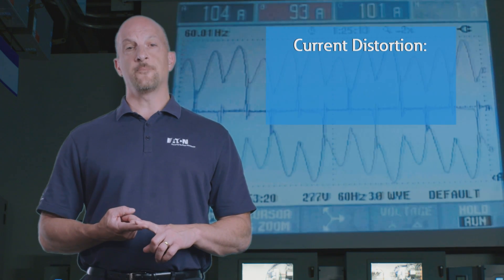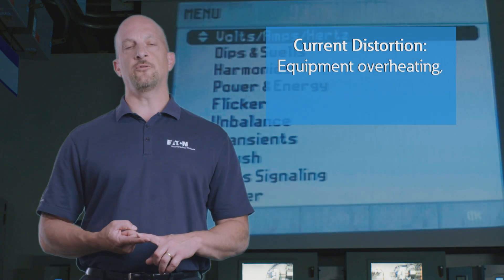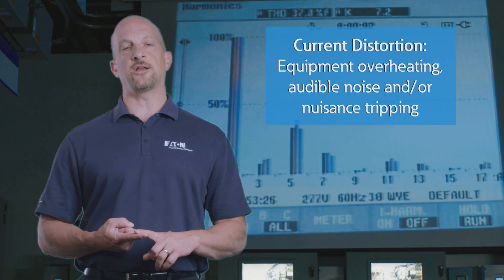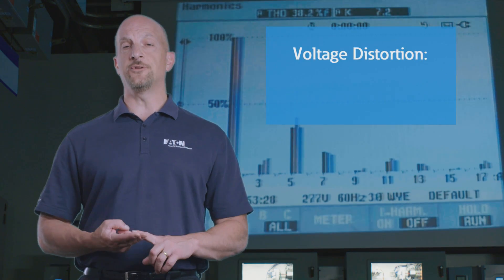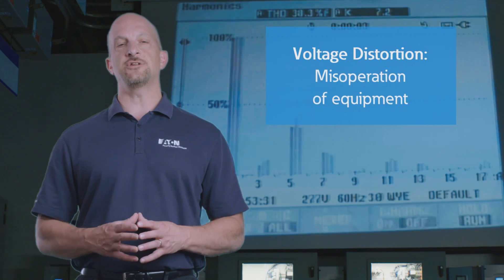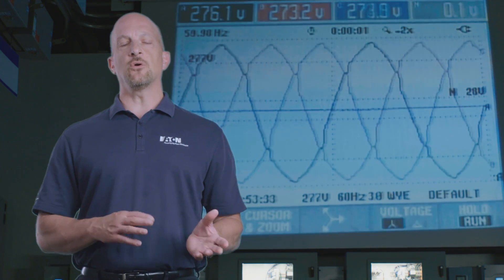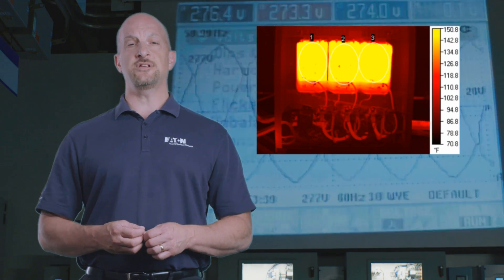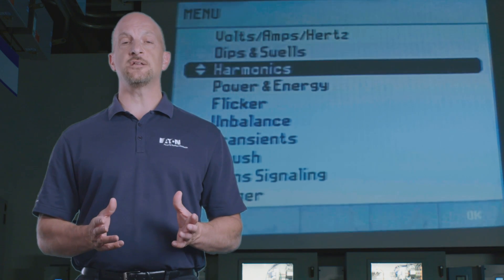Harmonics can create two fundamental issues. Current distortion, which has the symptoms of equipment overheating, audible noise, and nuisance tripping of protective devices. The second issue is voltage distortion, which typically causes misoperation in equipment. Either or both problems can cost you money with damage or misoperation to your equipment. But every system is different and careful analysis must be made, or you could significantly overspend on a perceived problem that may or may not exist.